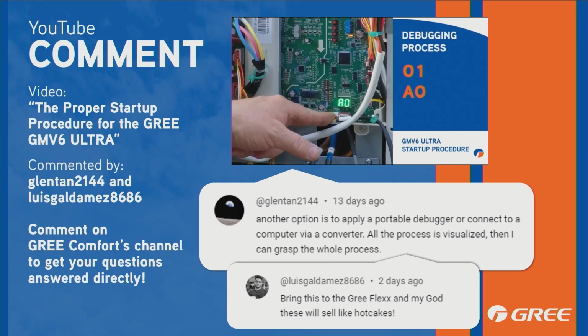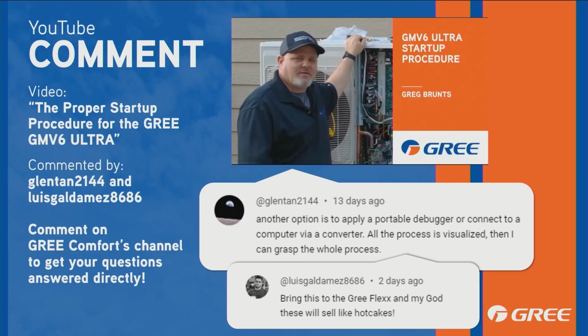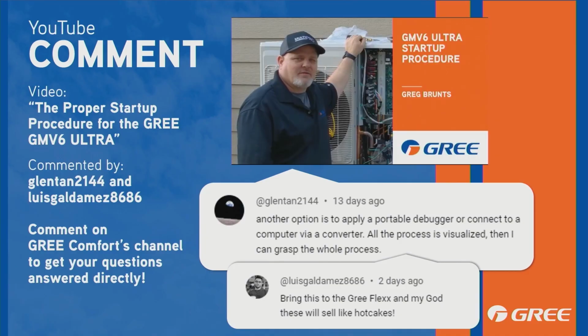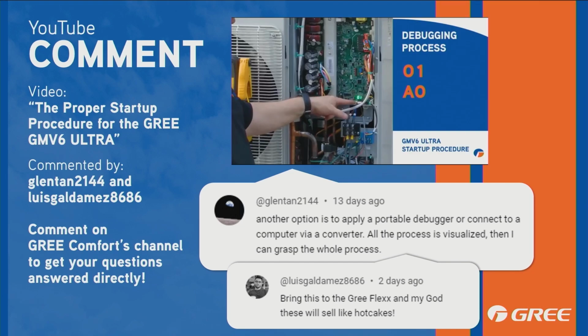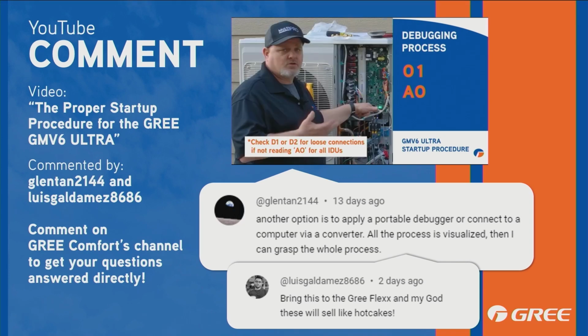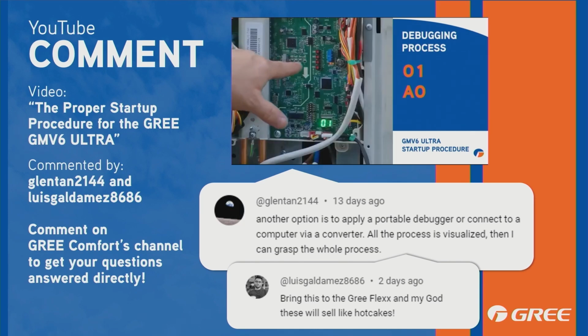We do have a portable commissioning tool that can connect to this, and it assists in the startup process of it. It is not required to use that tool for that startup process. It's a simple push button process, but either way, you can do that. The portable debugger also shows you your temperatures and your pressures for everything on the system. Now, I will say that you can also see all that information through a wired controller if your system has one. You can see the pressures, temperatures, the target compressor speed, the target hertz, your DC bus. Instead of pulling out a meter and measuring the DC voltage on your inverter board, you can see what that's being measured at the wired controller or at a portable debugger.